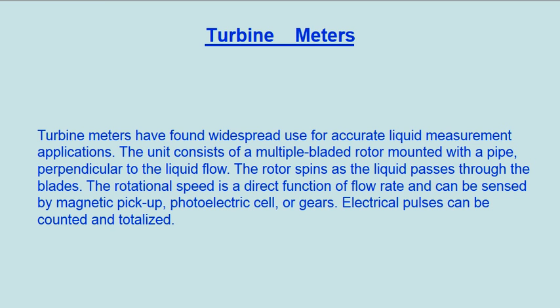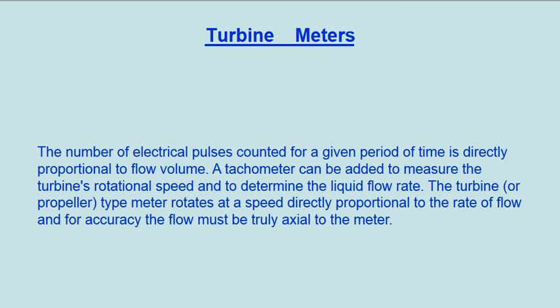The rotational speed is a direct function of flow rate and can be sensed by magnetic pickup, photoelectric cell, or gears. Electrical pulses can be counted and totalized. The number of electrical pulses counted for a given period of time is directly proportional to flow volume.